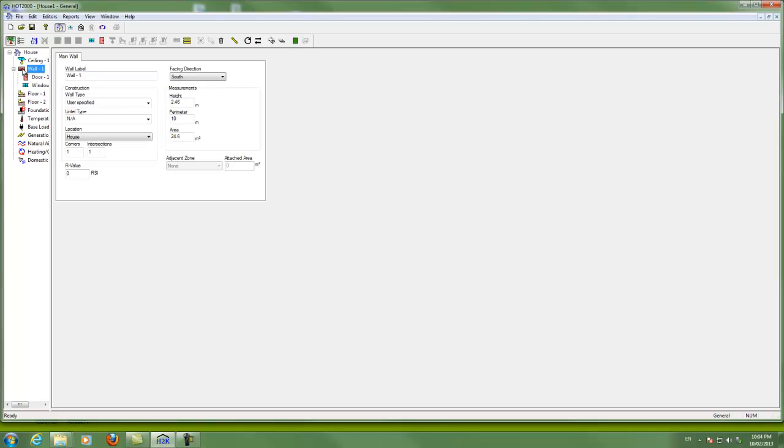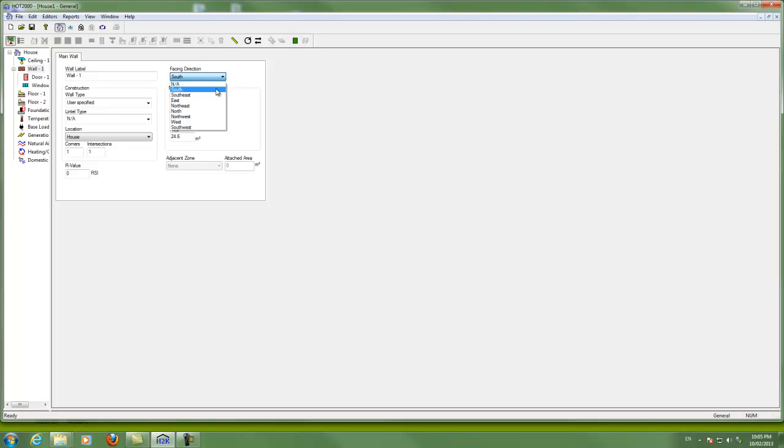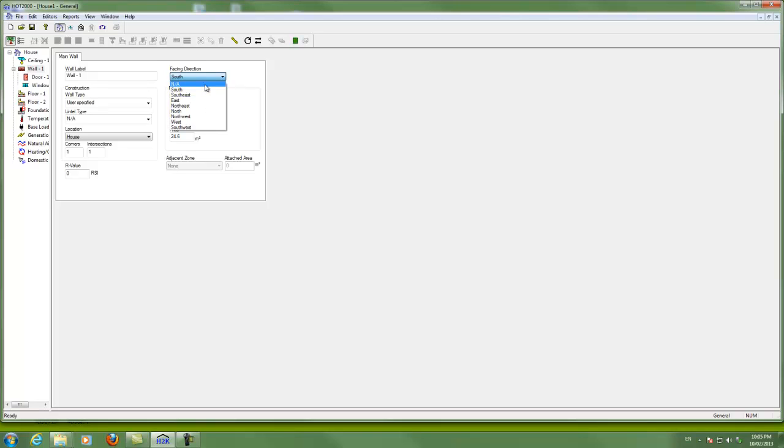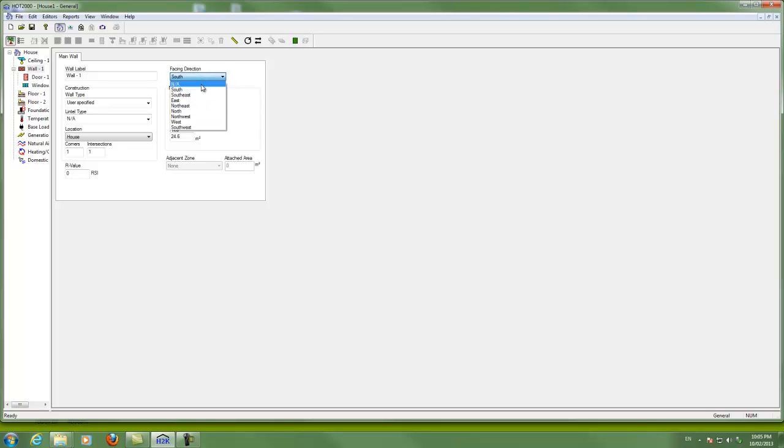A wall. Now walls are a little bit confusing. It asks for a direction. In fact if you read the help menus about direction, the program is not really calculating the heat loss any differently according to the direction here. If we have a bunch of walls that all have the same construction and the same R value as we usually do, you can choose NA here.